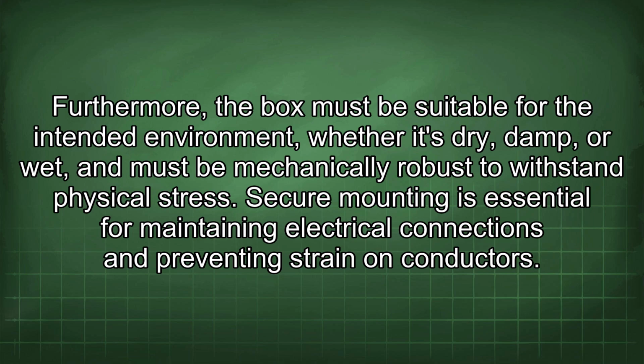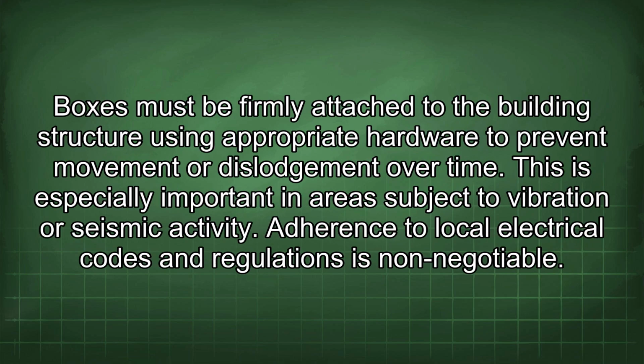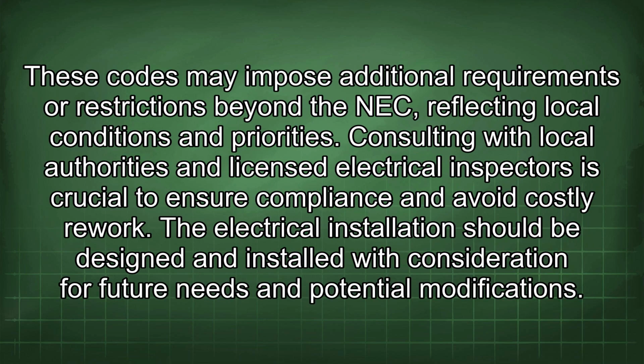Secure mounting is essential for maintaining electrical connections and preventing strain on conductors. Boxes must be firmly attached to the building structure using appropriate hardware to prevent movement or dislodgement over time. This is especially important in areas subject to vibration or seismic activity. Adherence to local electrical codes and regulations is non-negotiable. These codes may impose additional requirements or restrictions beyond the NEC, reflecting local conditions and priorities.